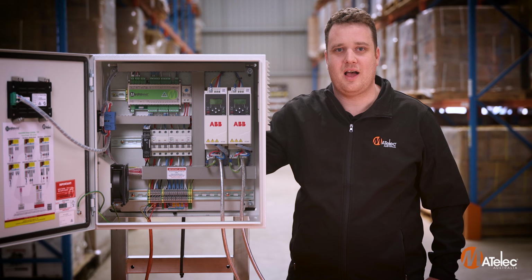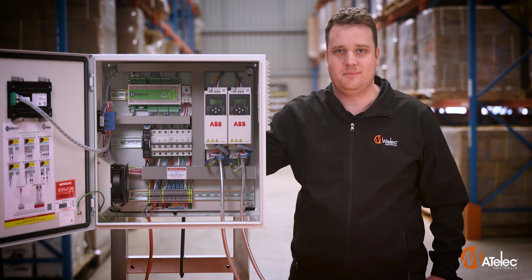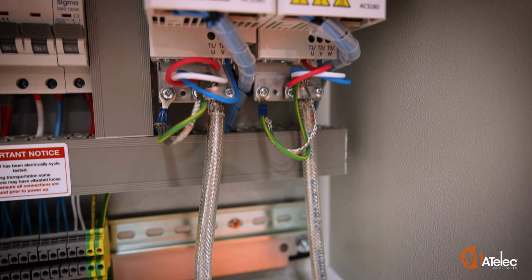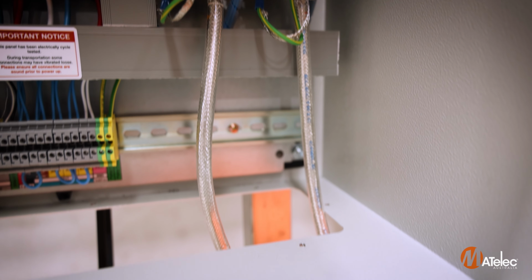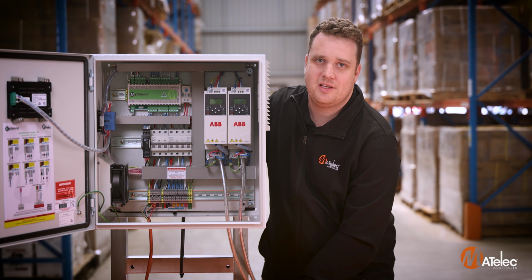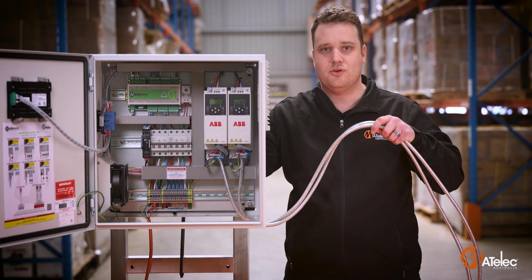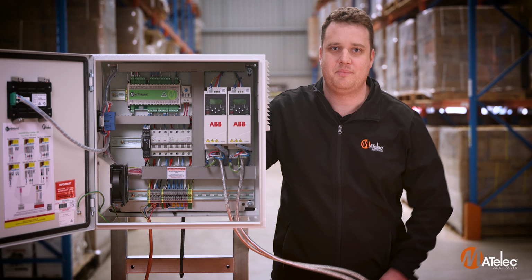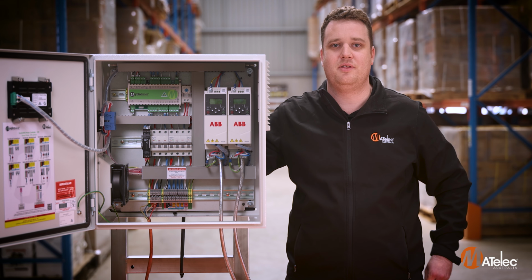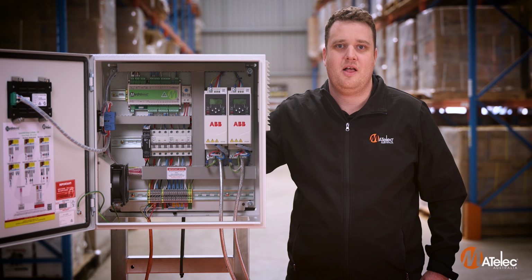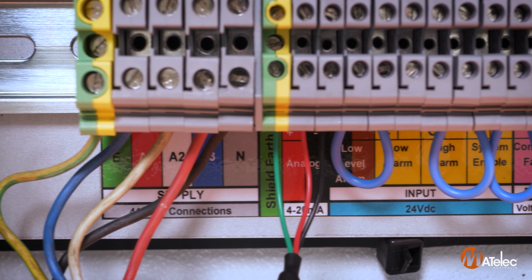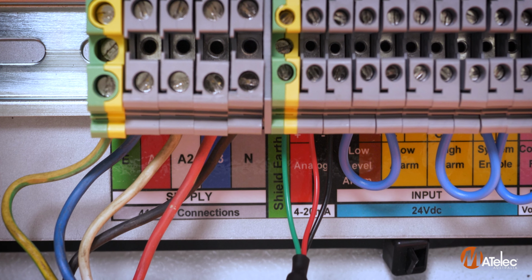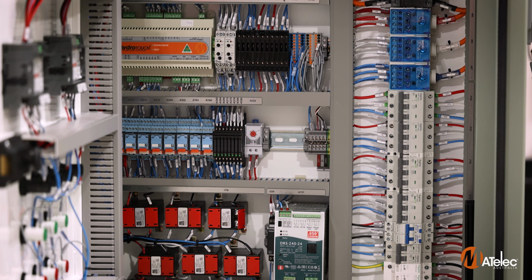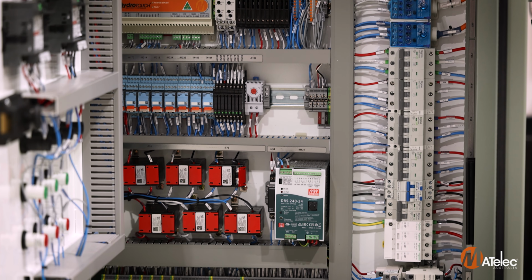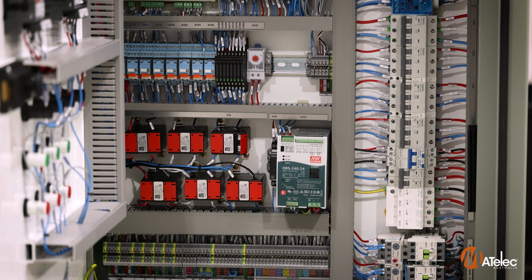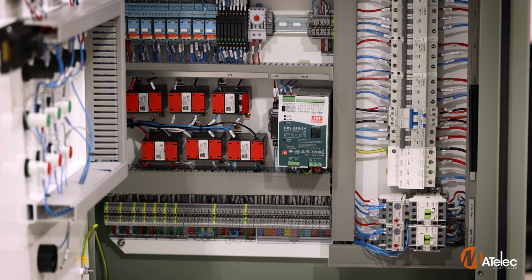Once you've finished setting up the input connections for your system, the next step is to look at the pump and power connections. Your HydroWHIZ panel comes with VSD cabling that is sized to the pump you'll be connecting. Make sure to connect the pump cable to the pump as per the manufacturer's instructions. The panel also has clearly marked terminals for the main power connection. On larger panels, these connections might be brought directly into an isolator or an MCCB, and earth neutral bars may be used in place of terminals.